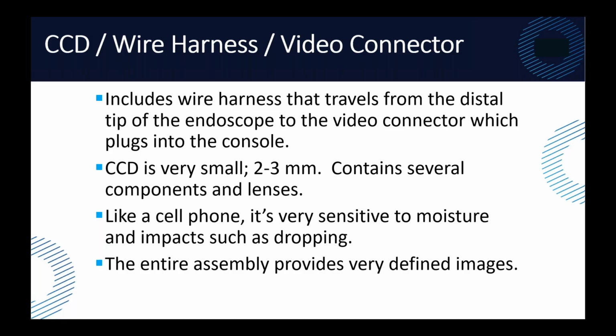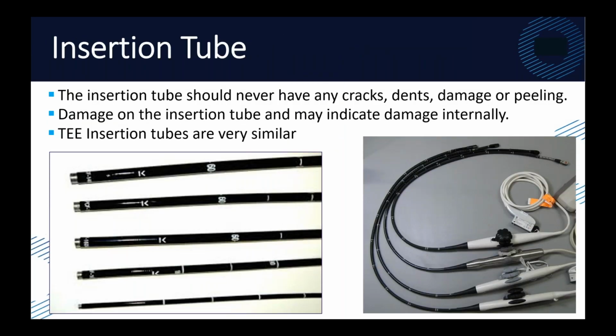Each one of these cameras also has several lenses. So you don't just have a chance to crack one thing, you have a chance to crack multiple. And any one of them that you crack is going to ruin the image. So they are very sensitive to moisture and impacts such as dropping. That's another reason we want to be very careful about handling. So the video connector in an endoscope is definitely one of the highest failure items for damage.